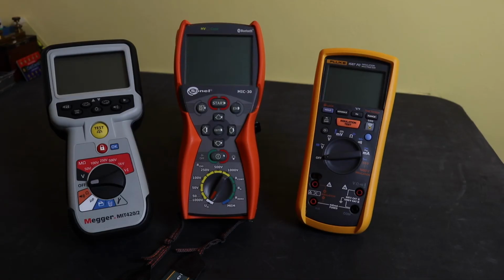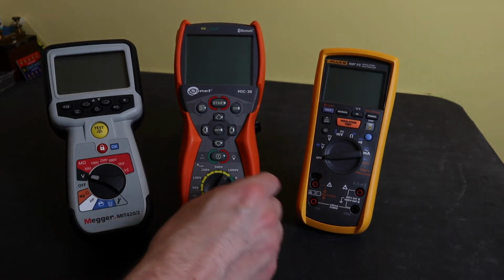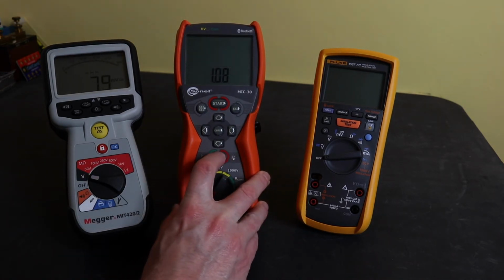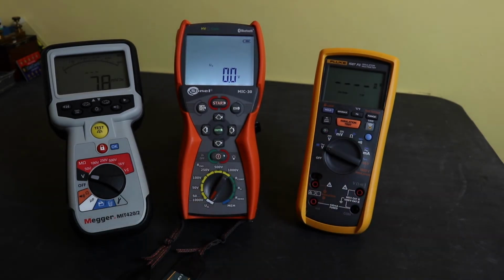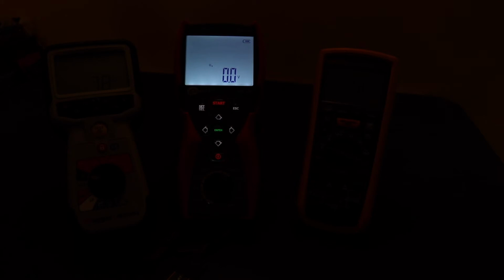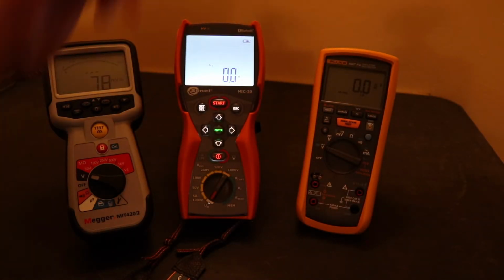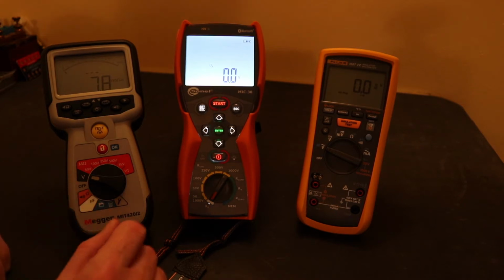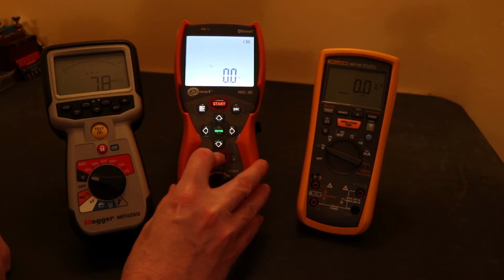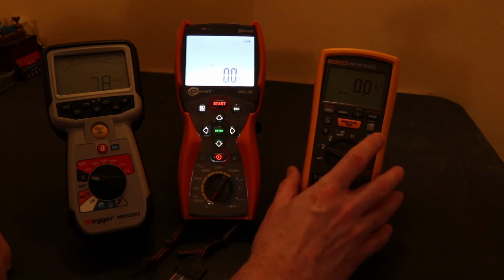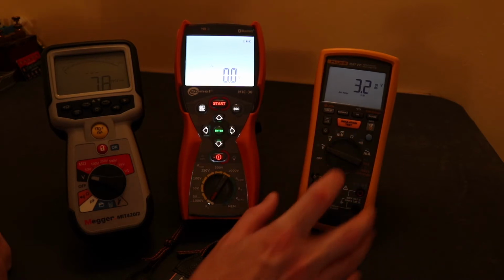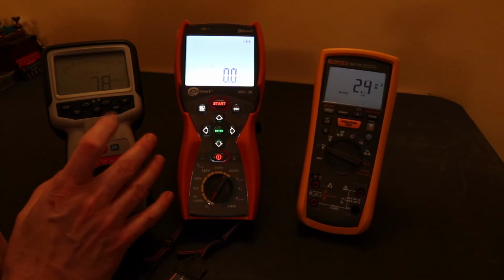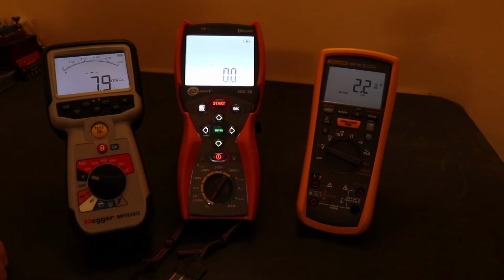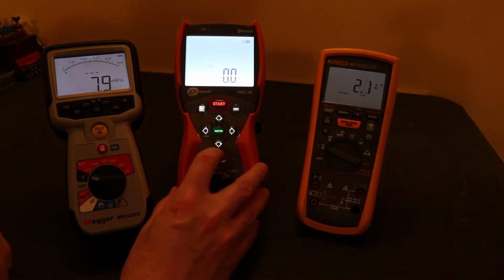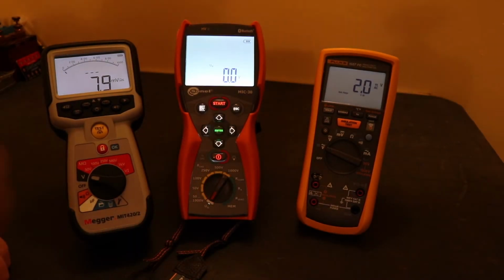Okay, looking at the actual instruments themselves, before I do anything else, I'm going to test the backlights just to show what they're like, because you know how poor I am at using up the batteries. Let's turn the backlight off and hopefully you can see a little bit better. You see the Sonel unit defaults to having the backlight on. It actually has two stages to the backlight. So that was stage 1, this is stage 2. In contrast, you only have stage 1 on the other two instruments. There's the Fluke, and there's the Megger, and then you can turn them off. So much brighter even on stage 1.